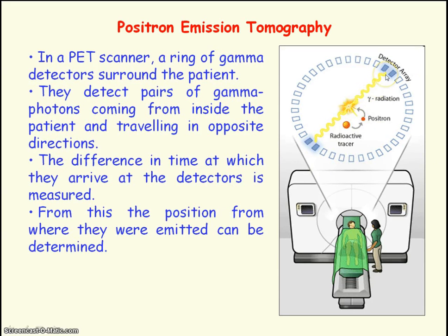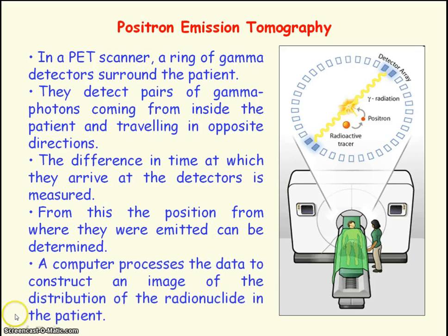From the delay time, the position where the gamma rays originated inside the patient can be determined. The gamma photon that arrives first at the detector will have travelled a shorter distance compared to its oppositely travelling gamma photon. Using the speed of the gamma radiation and multiplying by the delay time, you can determine the additional distance the oppositely moving gamma photon has travelled, and hence determine where the two gamma ray photons originated inside the body. A computer processes all this data to construct an image of the distribution of the radionuclide inside the patient.